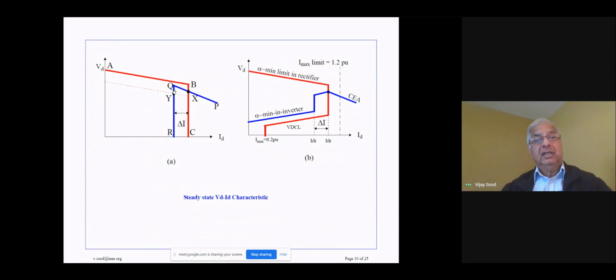So you can see that the control strategy can switch from the rectifier to the inverter, but you can still maintain transmission if there is any kind of fluctuation in the AC voltage at the rectifier. So this is the normal characteristic for a HVDC system. We can implement some more changes, some more modifications to this system. Those modifications are shown over here.